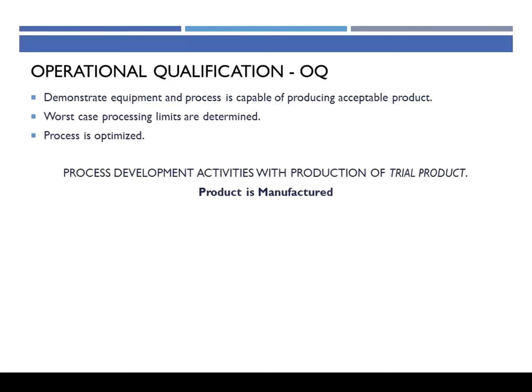What we want to do in this phase is establish our process control limits. So we want to take all of the process inputs, time, temperature, pressure, etc., and say these are our limits for this. We're going to run within this temperature range or this speed range. If the equipment contains software, we're going to want to validate the software independently.